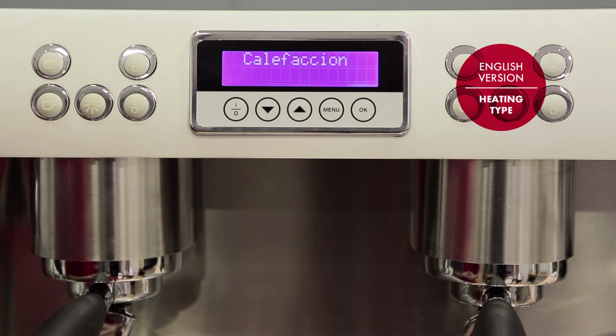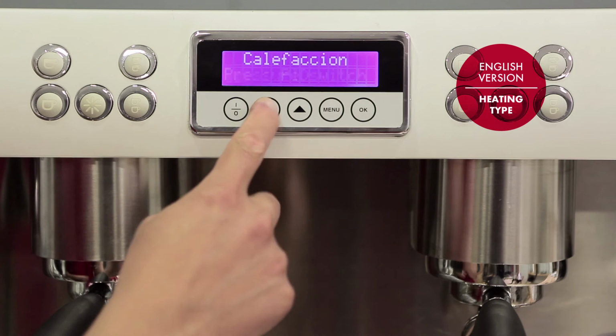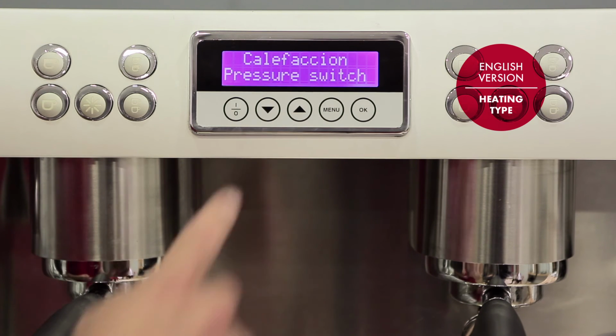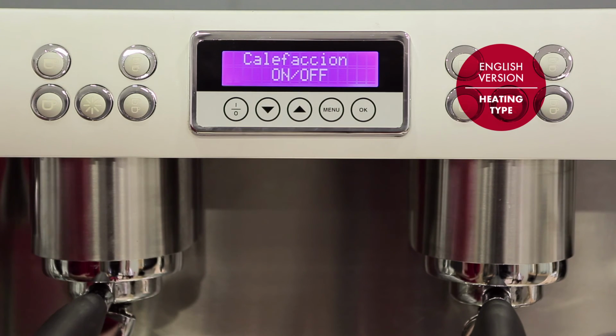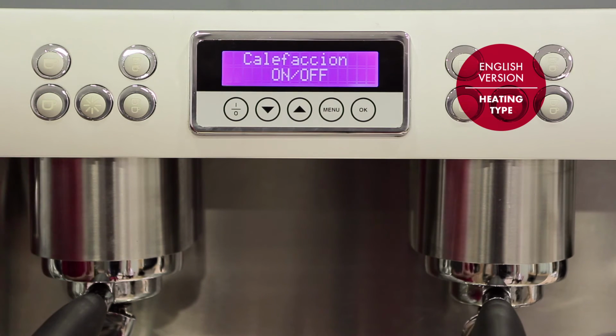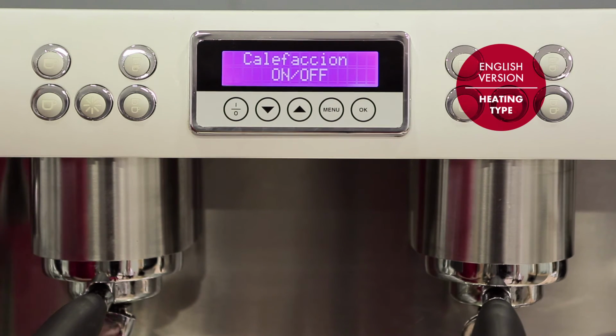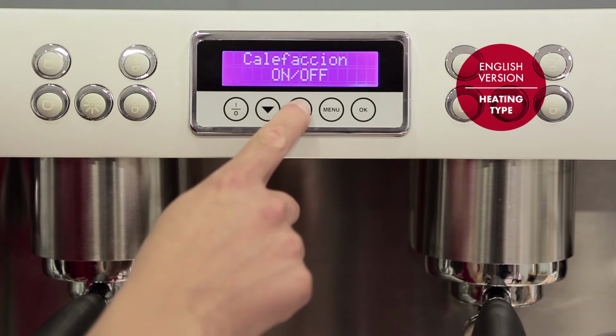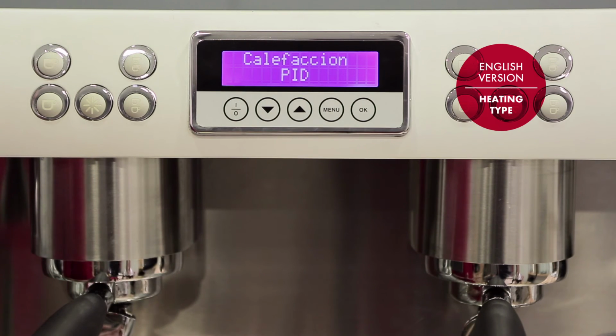The next function is the heating option. There are three options: PID, pressure switch, and on-off. If the machine we're working with is a machine that works with a temperature probe, we select the options of on-off or PID, programming the options that the machine prompts us for. Conversely, if the machine works with a pressure switch, we select the option pressure switch and we move on to the next function in the menu.